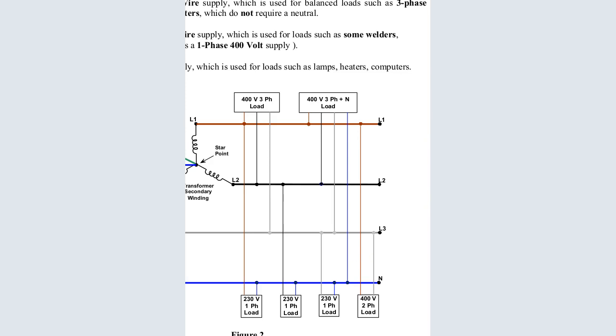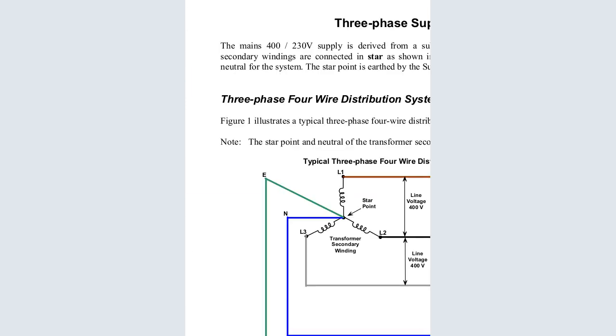At the same time, we can have one that is taking a single live phase. Remember, all our single phases must have a neutral. So this one, we are tapping this. This is a single load, tapping one of the lines. This one is now lighting, like the lights, the computers, the iron boxes, and all those. They tap the single phases. These are what our sockets normally have in our homes. You can tap it from one phase. Another load, you can tap the second phase. Another load, you can tap from another phase, so that you can balance. This is called a single phase.